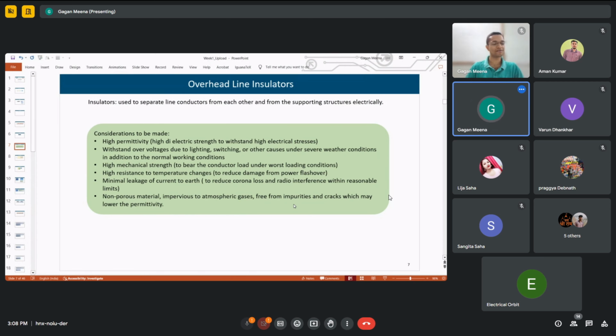So the tower has to carry so much mechanical load. The insulator should have high mechanical strength to bear that load, even under worst loading conditions, such as during stormy weather, or in India, especially in the Himalayas, where there is icing. When ice covers the conductors, the mechanical load increases, their weight increases. So that also the insulator has to bear. All these considerations need to be taken care of while designing these insulators.